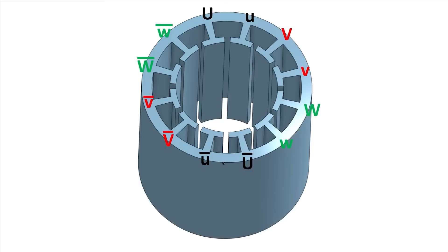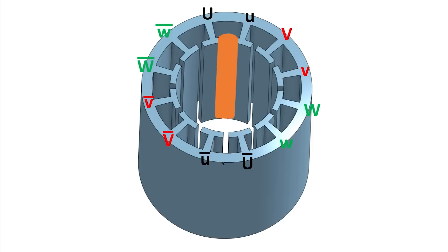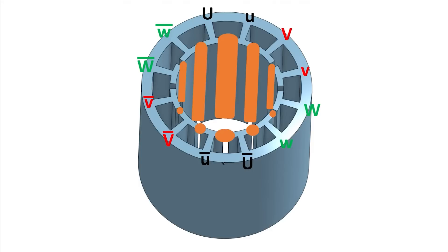So now we'll get a strong magnetic flux between each of these poles on the stator. And by injecting more or less current into each winding, the drive can very accurately control the amount of magnetic flux between all these poles. So for example, what we would expect to see is a really strong flux here, smaller here, smaller here, and the inverse of that on the other side to create a super strong magnetic field to position the rotor.